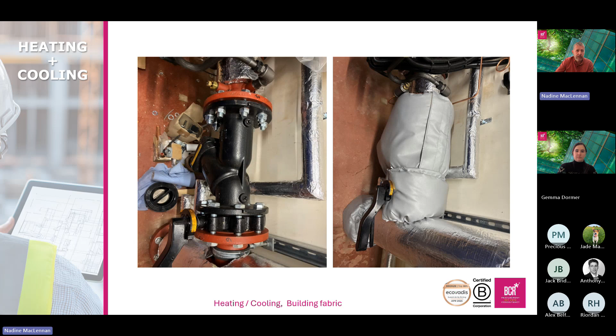In the same boiler room, the installers did put some insulation in, as you can see the silver foam bits around the pipes, but didn't go that one extra step of the hassle and expense of lagging the bronze valves. That should look like this - again, it's hemorrhaging your money into the boiler room when that heat should be traveling around your building, heating your staff. Now there's a number of areas we look at.